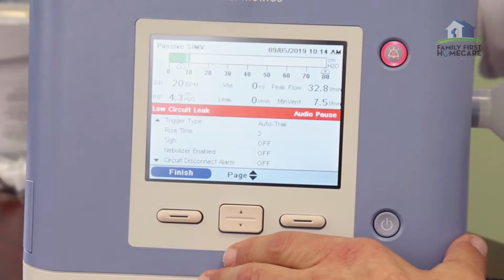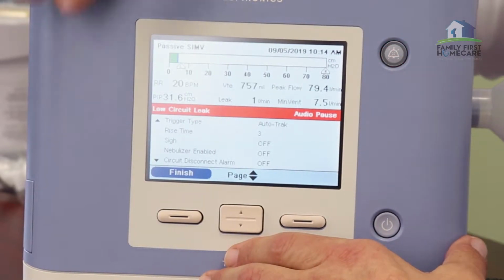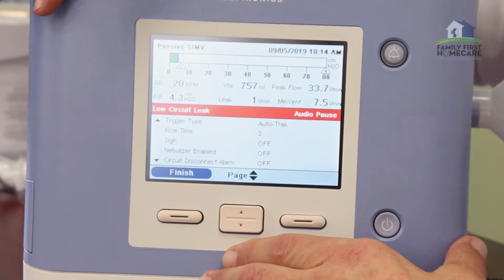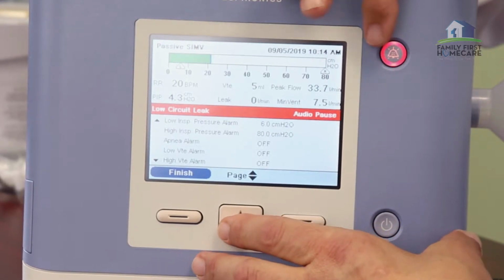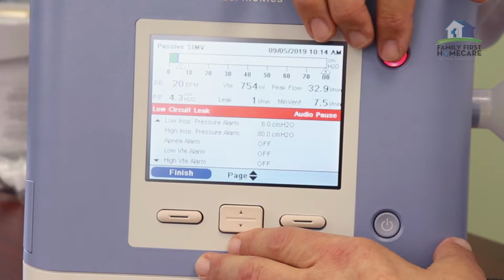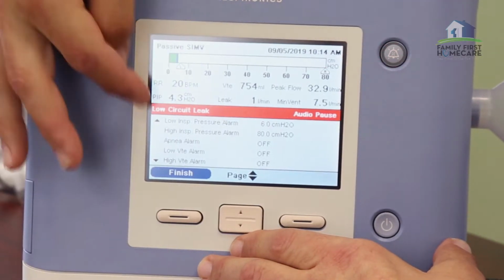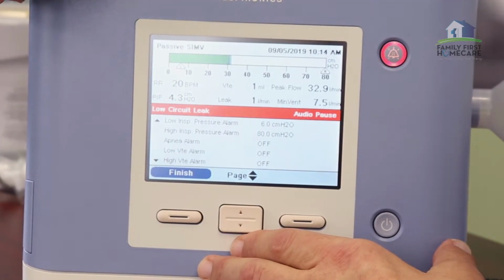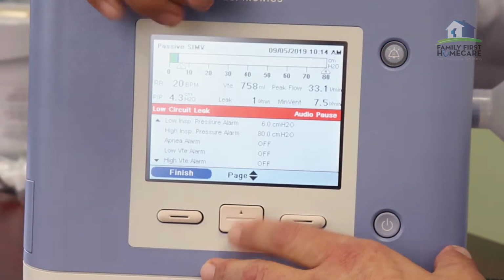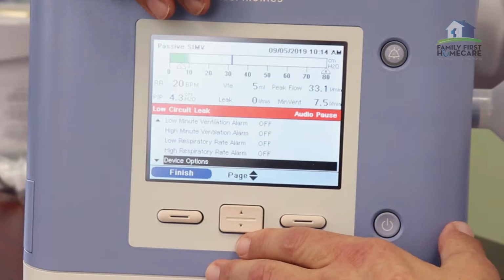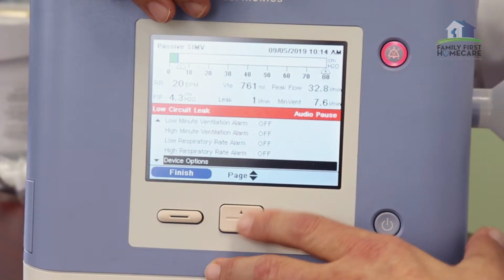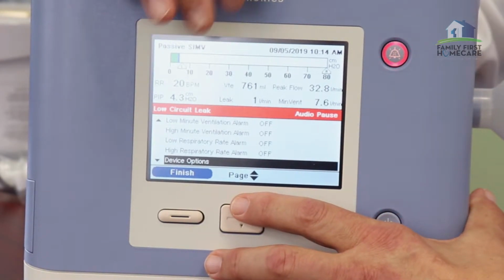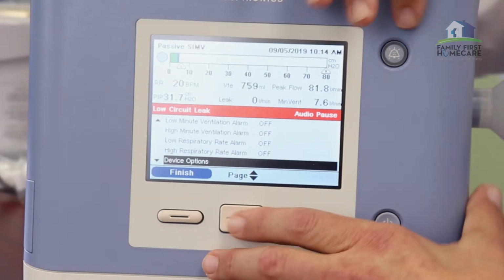Now, those are your settings. You can verify them simply by going to information. Have no fear that you're going to change anything. Continue going down, and you'll be able to see which alarms are on. You'll see that I have 2 alarms set. One is a low inspiratory pressure alarm of 6 and the other is a high inspiratory pressure alarm of 80. But there are many different alarms that can be used. So depending on what your doctor orders, that's where you'll find the alarms.